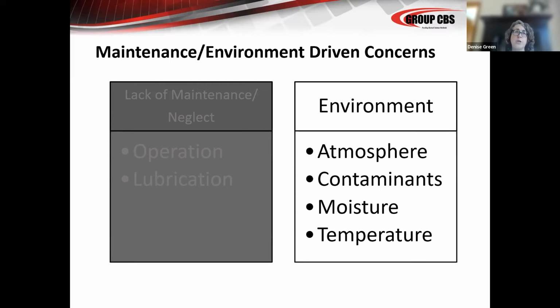We talked about moisture a little bit, whether that be an active moisture leak or whether the moisture is a result of the environment, whether your heater strips are not on, whether you have a heater strip located in an area that can potentially cause damage to the breaker. I saw a failure where heater strips were mounted on the side of the cells very close to the GPO3 barriers of the breaker instead of down below that.